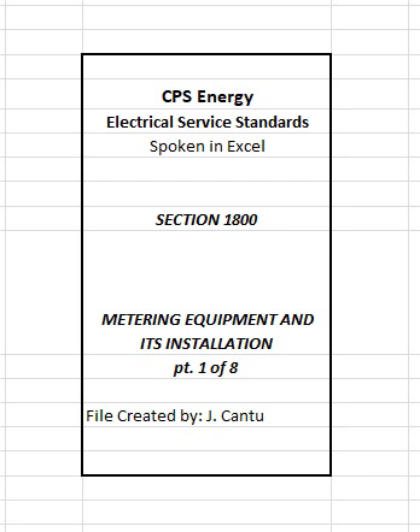Note: in no case will customer be authorized to bypass a meter socket or other metering equipment to provide unmetered service. 1. Conductor identification. Customer line and load conductors must be identified at their terminations in accordance with Section 400 of these standards. Terminals so identified will be evidence of customer's intended phase sequence, high leg position, plus position of other phase conductors and the neutral conductor. Meter loops lacking proper conductor identification will not receive a CPS Energy meter. Customer assumes all responsibility for conductors that are improperly identified or terminated.